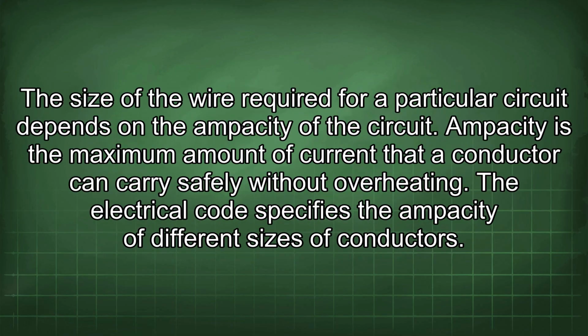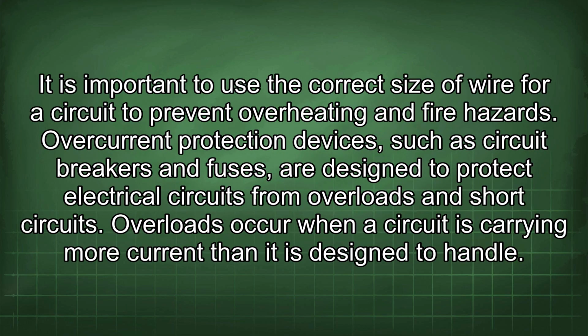The size of the wire required for a particular circuit depends on the ampacity of the circuit. Ampacity is the maximum amount of current that a conductor can carry safely without overheating. The electrical code specifies the ampacity of different sizes of conductors. It is important to use the correct size of wire for a circuit to prevent overheating and fire hazards.